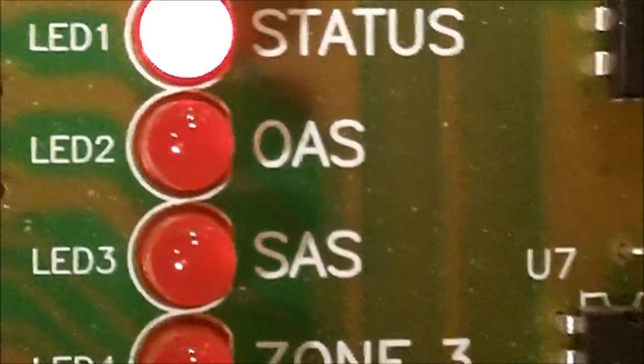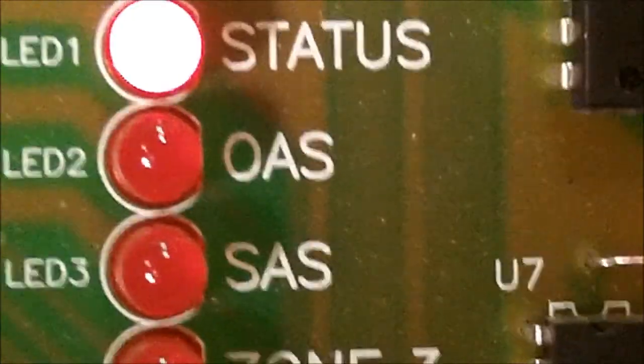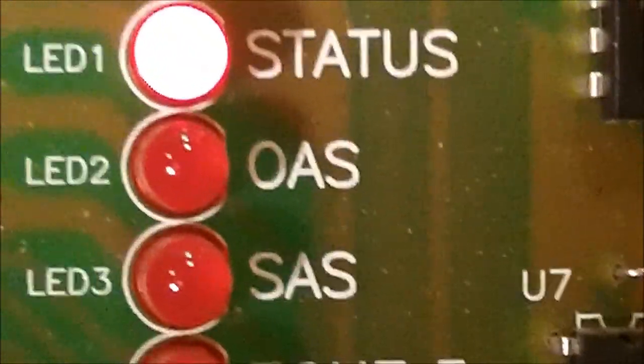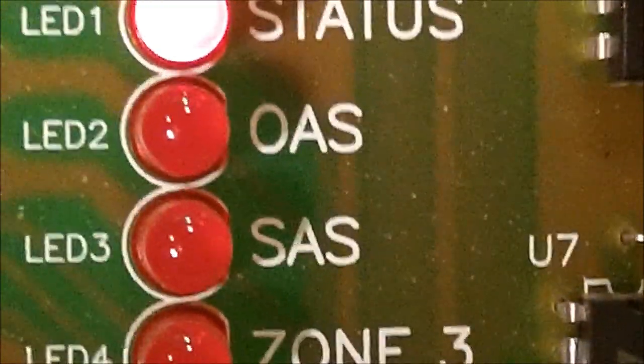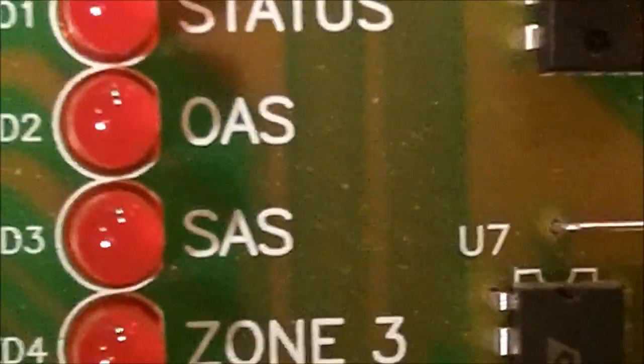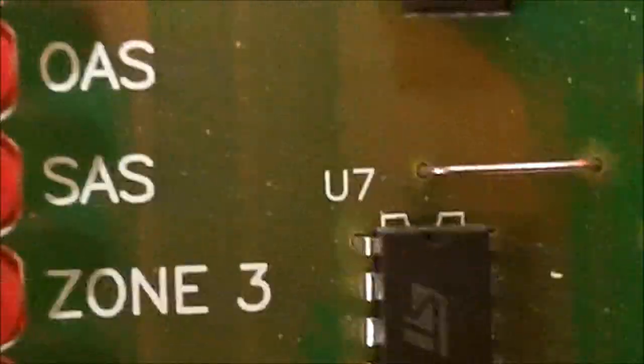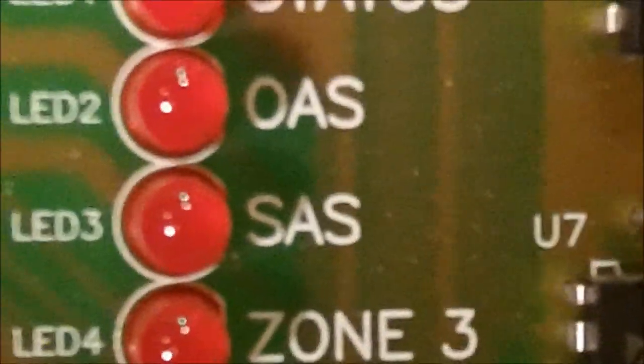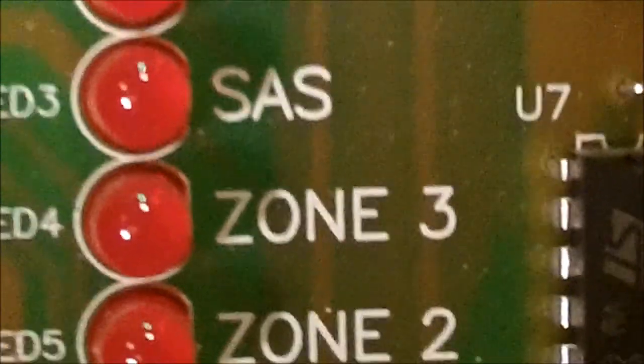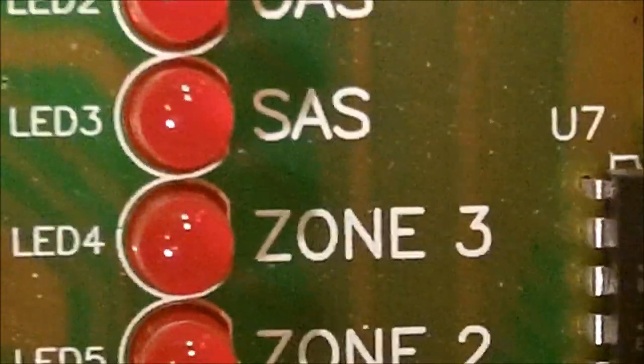If you come and the thing is not running, and you get up here and the OAS light is flashing, check your outdoor sensor, the resistance on it. Your next one, of course, is your supply air sensor.